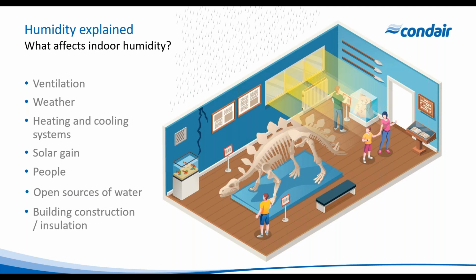And of course, then there's building construction and insulation, and this can have an effect. More typically for high humidity applications, because certainly in the UK, if you've got poor building construction or poor insulation, then there's the potential for cold bridging across building materials. And when you get that, there's the potential to have a cold surface. So if you have a cold surface that's below dew point, and we know the dew point is 10.5 degrees C at 21 degrees C and 50%, then any surface that's below the dew point of 10.5 degrees C has the potential for condensation to occur, and that is when we get into potential mold growth. So building construction can also have an effect.